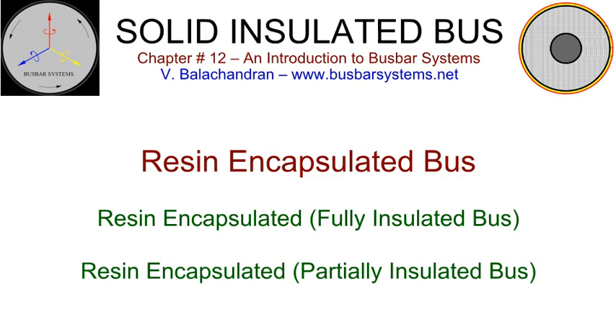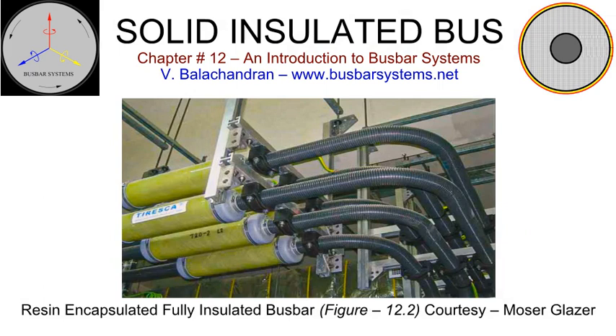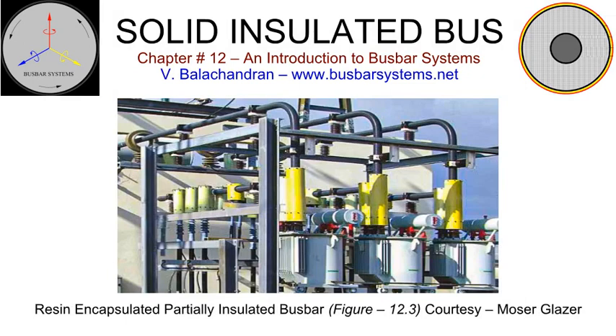The laminated conductors cater to the linear expansion and contraction of the conductor due to temperature variation, based on the insulation level of the encapsulated conductor. They can be classified as fully insulated bus and partially insulated bus. Resin encapsulated, fully insulated bus: the conductor is encapsulated suitable for a voltage of 3.6 kV and a basic insulation level. Resin encapsulated, partially insulated bus: a conductor is encapsulated to withstand a voltage of 7.2 kV with a 1-minute power frequency withstand voltage of 28 kV. These conductors, though insulated for 7.2 kV system voltage, can be used for a system voltage up to 36 kV by mounting them on an appropriately rated insulator.